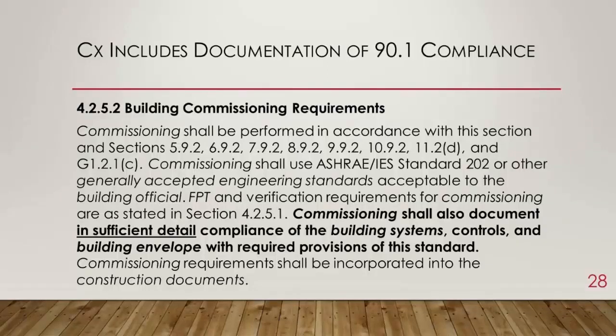So we are requiring that some level of commissioning include the verification of 90.1. Now, you can certainly write your scope however you write it, as long as you aren't actually verifying full code compliance. We use the words in sufficient detail. In other words, a good effort is made to verify that this set of construction documents does meet 90.1. We think those words were added to indicate that you don't have to totally verify every tiny detail, but we do want a general verification that 90.1 requirements are being met.